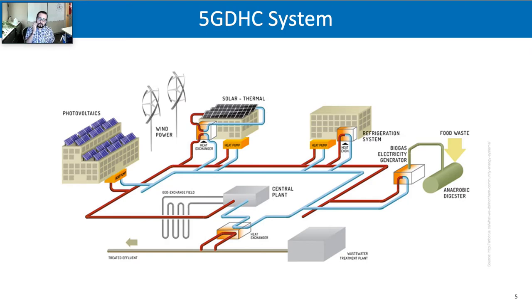The advantage also is that you have more temperate water available, so waste heat becomes attractive to systems that originally wouldn't be rejecting waste heat into a district system. A condenser of a refrigeration system can now dump its heat in there, or a waste water treatment plant can dump its heat into there, because low-grade heat is actually of use.